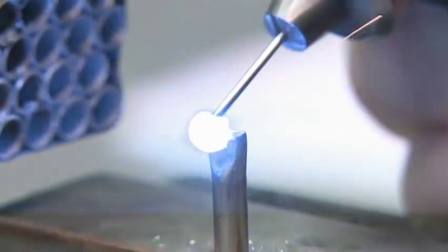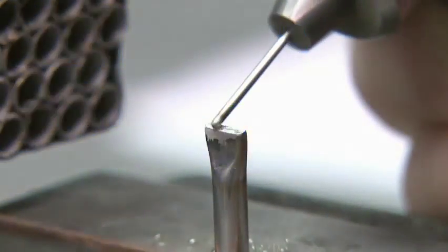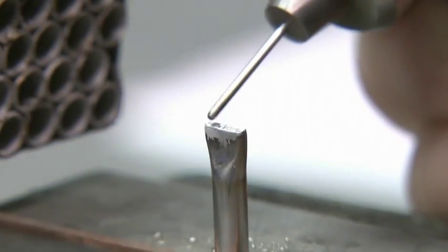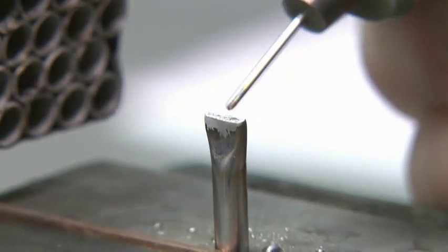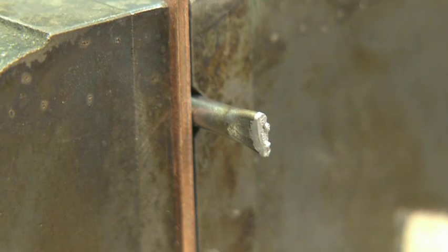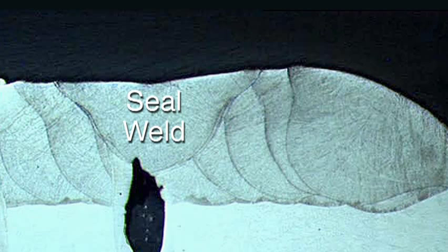The insertion tube for the container is made of 304L stainless steel. An ESD — electro spark deposition — technique is used to increase the chromium content of the 304L stainless material by alloying a higher chromium 312 stainless steel filler metal to the surface of the container. This technique changes the crystal structure in a region of the material so that no solidification cracking occurs when a seal weld is created.